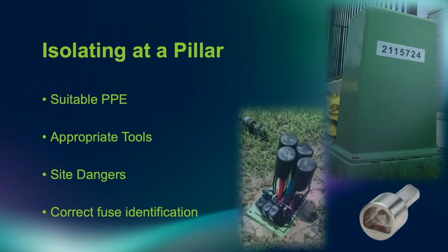Some extra precautions, though, do need to be taken when you are working at a pillar, as they can contain exposed live parts near your work area with a high fault current potential that is significantly closer to you when compared to a pole. Additionally, they should never be left uncovered whilst unattended. If you do need to step away, the pillar should be reinstated with its cover and the retaining bolts put back in as well.